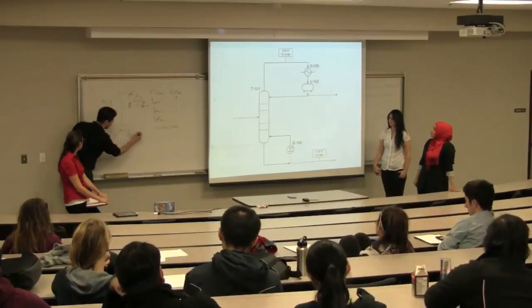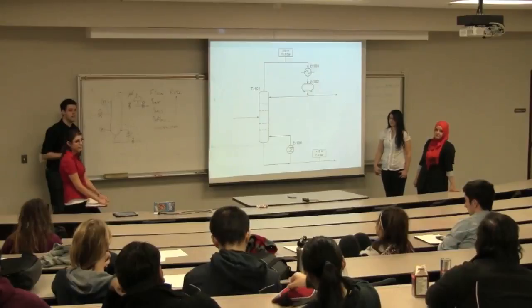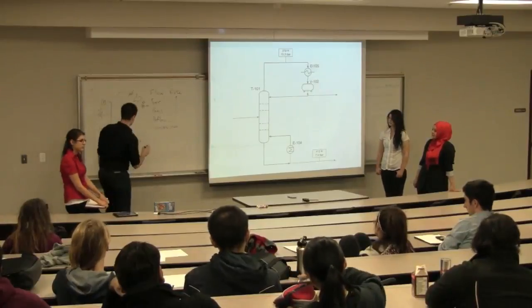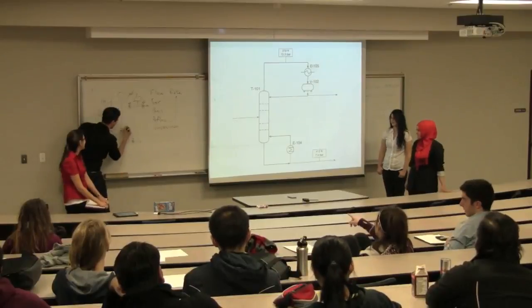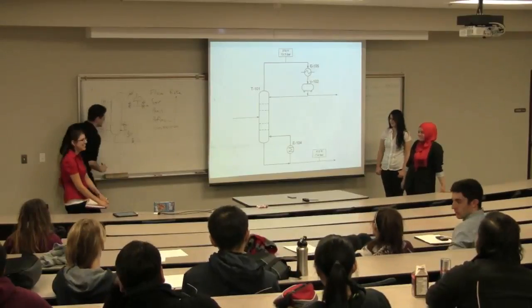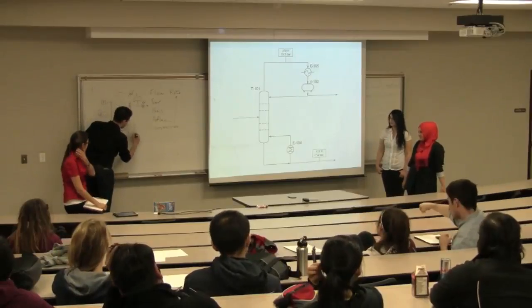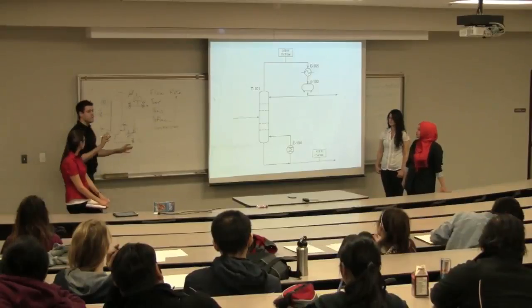How about in this section of the flow sheet right there? Where would we put a temperature transmitter? What would we do with it? Probably right before that valve. Right before the valve? Actually, no. What I was going to tell you is that we would put a temperature transmitter right here. And this is going to feed back to a control valve, letting the steam in and controlling our thermal siphon reboiler. So that's really good ideas.